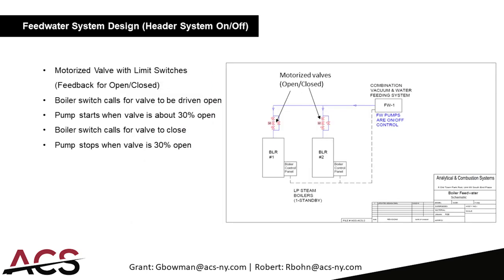In the header feed water system with on/off pumps, all pumps are piped into a feed water header, making them redundant to each other. Between the pump and the header and the boiler there's a motorized ball valve with limit switches for feedback of open/closed back to the controller. The feed water valve modulates based on the float or probe on the boiler itself. There is also a piped bypass around the control valve so that if the control valve fails, you can still run it with just the ball valve in case of emergency.